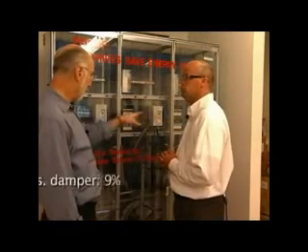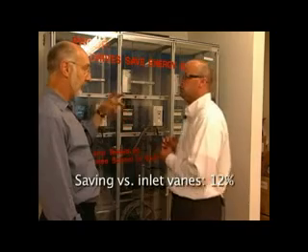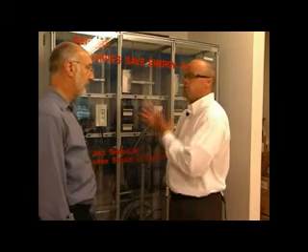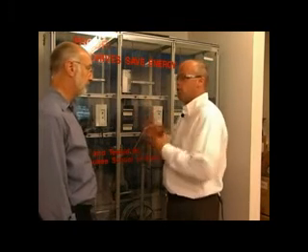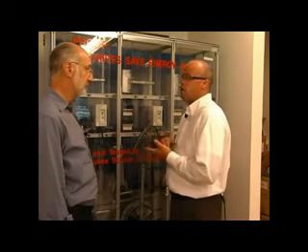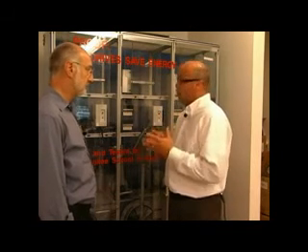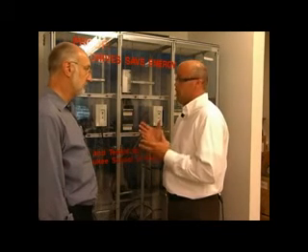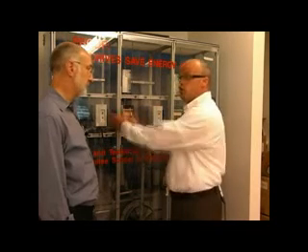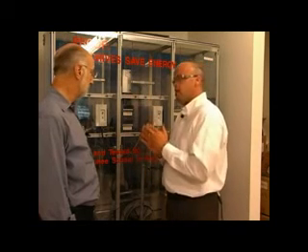Now we saw the difference in the motor, but is the difference in the horsepower actually indicative of the actual current draw? Yes. With today's pumps and VFD control, it's pure physics when it comes to the affinity laws of these type of applications used in industrial facilities. We know that flow is directly proportional to speed. We know that power, though, is the cube of the speed. So in this last cell we were running the motor only at 36 hertz, where these two motors were running at a full 60 hertz across the line. So at that 36 hertz, when we're running at that type of speed, our energy savings and our watt consumption goes way down.